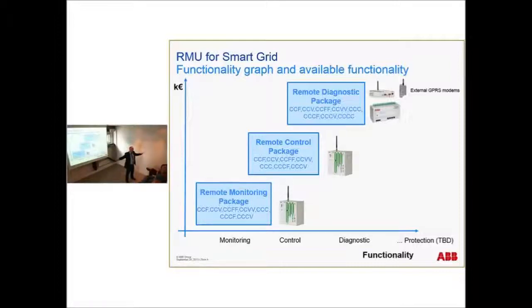You should not switch the load break switch. In cases where you have a vacuum circuit breaker, the switching is done inside vacuum, so then you could operate the vacuum circuit breaker. But in Iceland, the line switch is SF6 insulated, and that's why we say, as a supplier, you should not operate the switchgear. You should disconnect it, and you should phone ABB and tell us that there is a leakage.